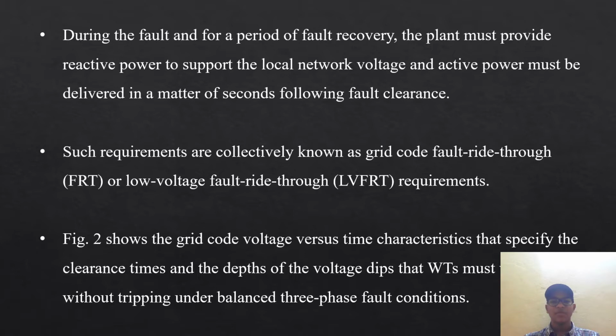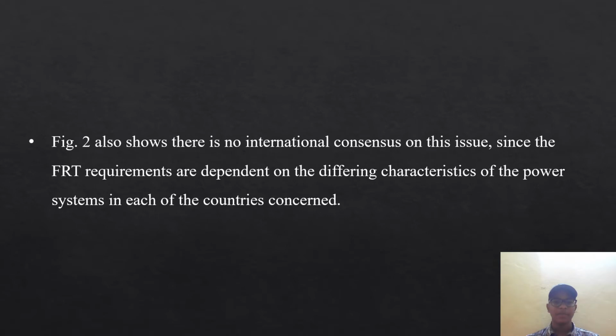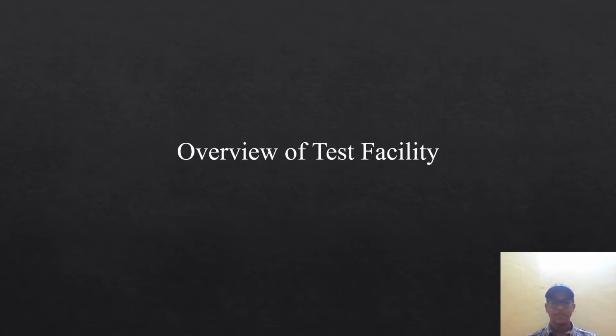Figure 2 shows the grid code voltage versus time characteristics and specifies the clearance times and the depths of the voltage dips that WTs must ride through without tripping under balanced three-phase fault conditions. Figure 2 also shows there is no international consensus on this issue, since the FRT requirements depend on the different characteristics of the power systems in each of the countries concerned.